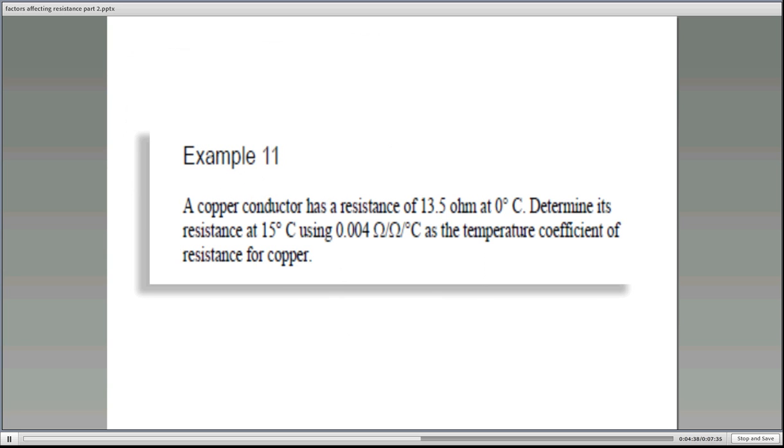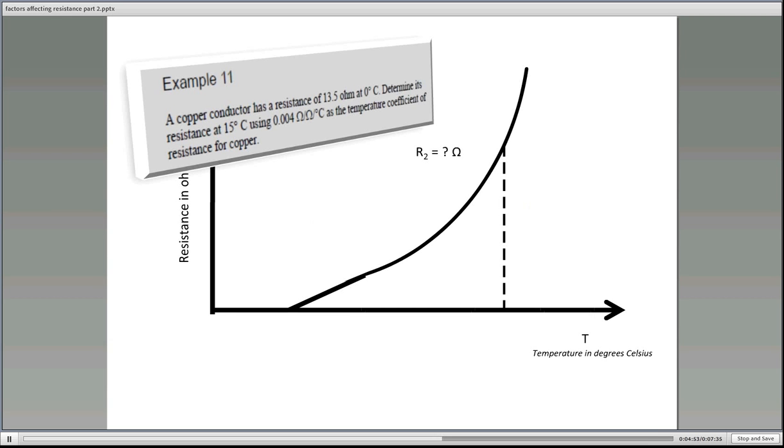So here's an example. A copper conductor has a resistance of 13.5 ohms at zero degrees. So determine its resistance at 15 degrees using 0.004 ohms per ohm per degree Celsius as the temperature coefficient of resistance for copper. So here's the information here. We're going to actually fill out this graph here. So there's our equation.